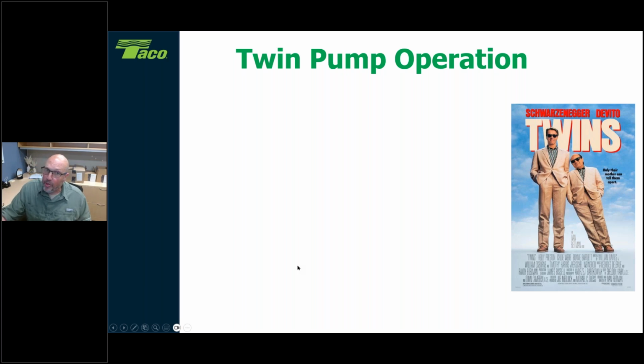All right. Now, another really cool operation of this circulator is that you can use this in twin pump operation, which means you can put 2 pumps in and you have automatic operation and you don't need an external controller. You're actually just running a cable between the 2 circulators. All right, and that's it, and we have everything built in. So what can you do in the twin pump mode? Well, you can have one circulator as backup, and we run into that quite often. We want to have a second circulator automatically turn on if one fails, if it stops working. So you can do that backup operation, and that will kick in really fast.